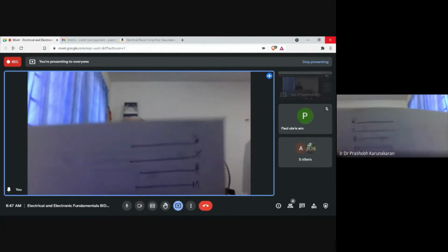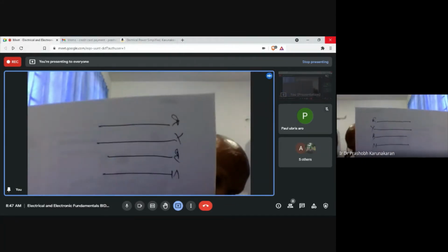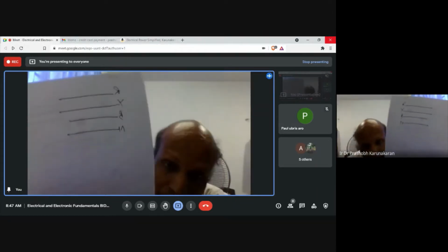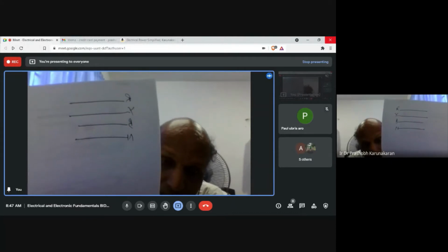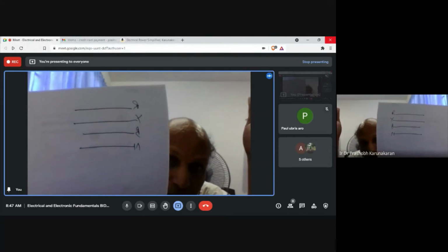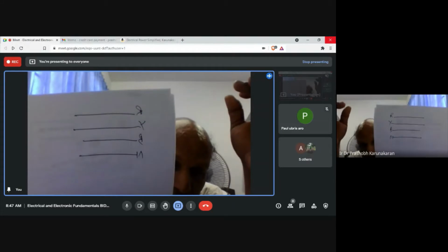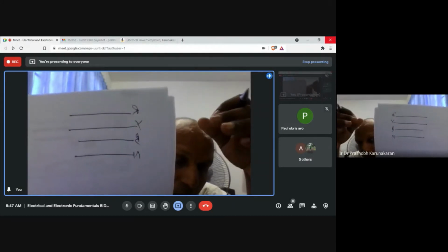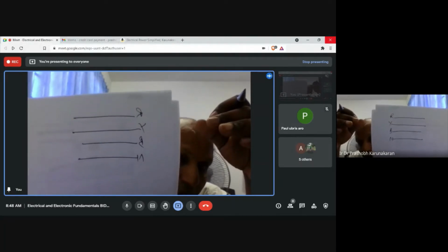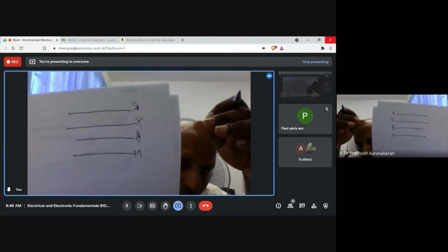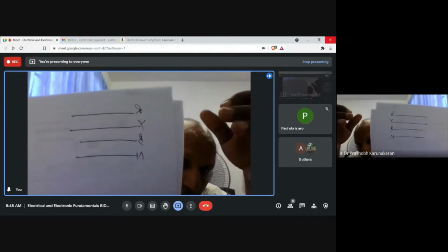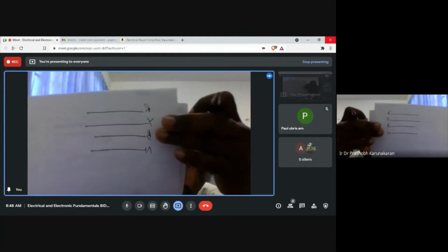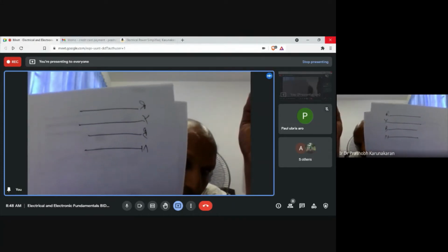You see, the wires coming out of Bakun is like this: red, yellow, blue, and neutral. Of course, the wires are not colored on the overhead line. But when they go inside the factory, they use the wires red, yellow, blue, neutral. In fact, it is a requirement. In the factory, you need to use different color. If red phase, you must put red wire. Yellow, blue, and neutral are normally black color.